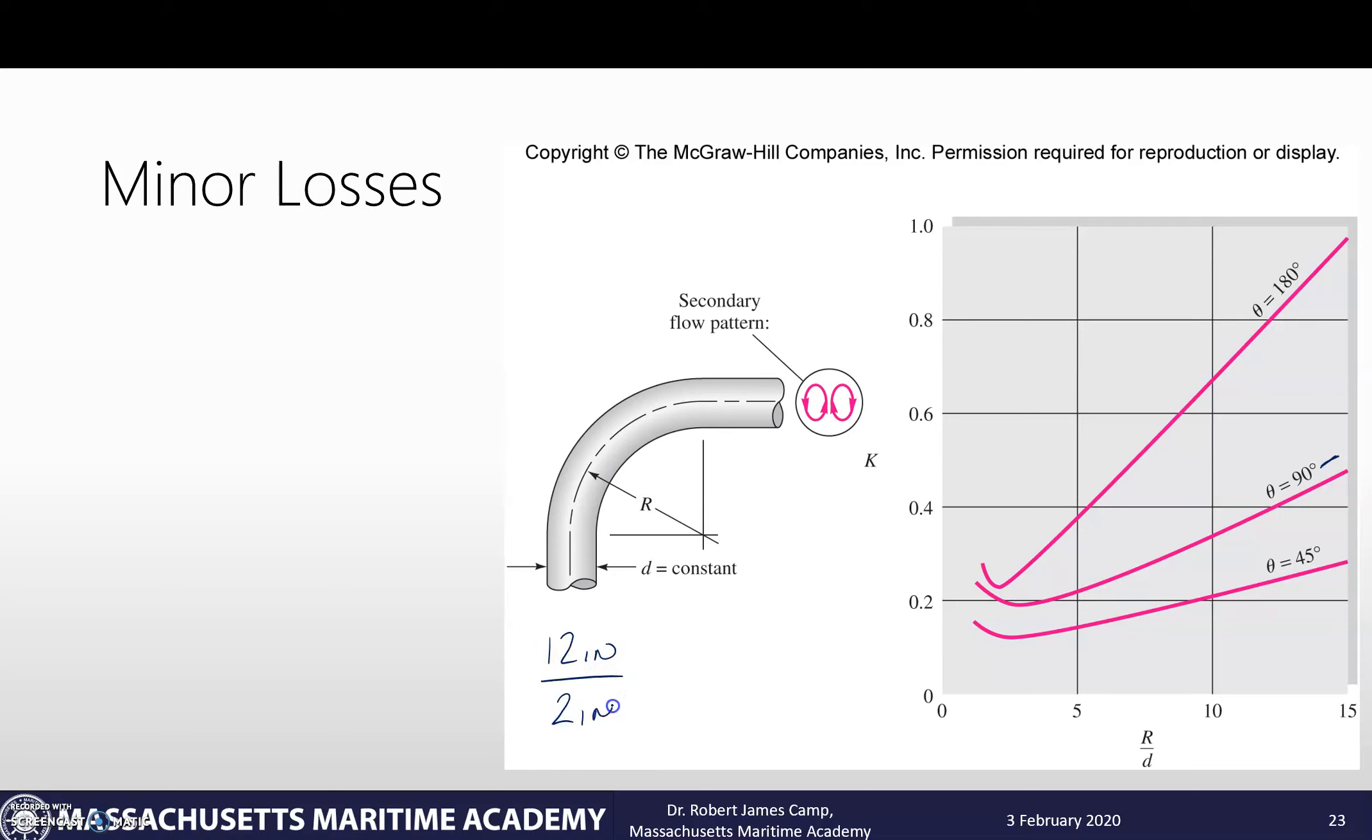And d is our diameter which is 2 inches. That gives us a factor of 6. So if we take a look at 6, that puts us about right there. Now we read over here, and that's about a quarter of the way up. So we'll say that our loss factor for our 12 inch bend radius is going to be about 0.25.